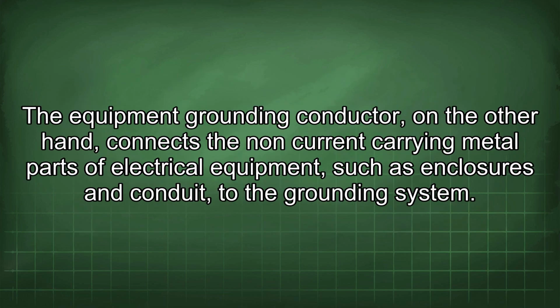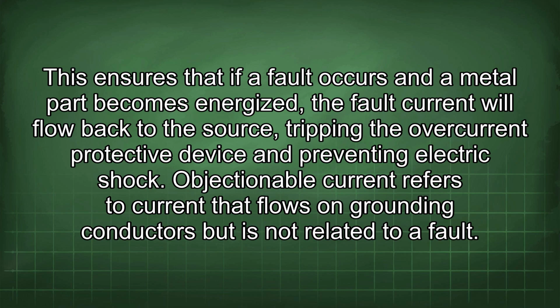The equipment grounding conductor, on the other hand, connects the non-current carrying metal parts of electrical equipment, such as enclosures and conduit, to the grounding system. This ensures that if a fault occurs and a metal part becomes energized, the fault current will flow back to the source, tripping the overcurrent protective device and preventing electric shock.